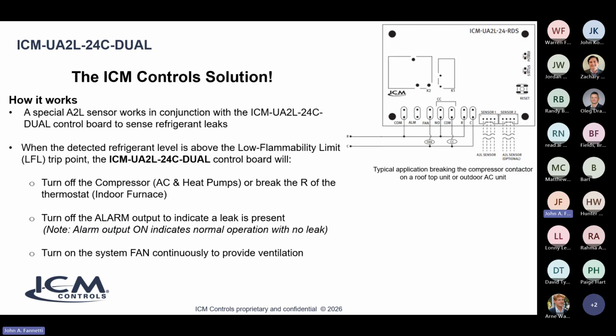So ICM Controls has a solution, right? So how does our solution work? Well, we came out with the ICM UA2L-24C-dual for aftermarket residential and light commercial applications. And how it works is there's a special A2L sensor that works in conjunction with the ICM UA2L dual control board to sense the refrigerant. So when a leak is detected, when that detection level is above the low flammability limit trip point, then the ICM product can turn off the compressor on AC and heat pumps, or break the R of the thermostat for an indoor furnace application. They will turn off the alarm output to indicate that a leak is present.